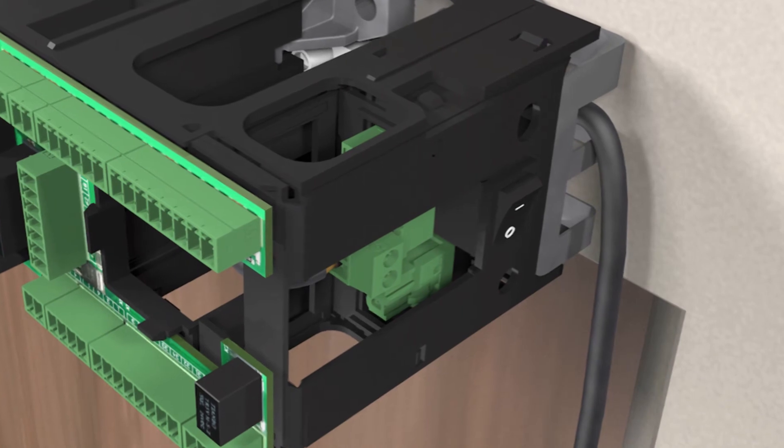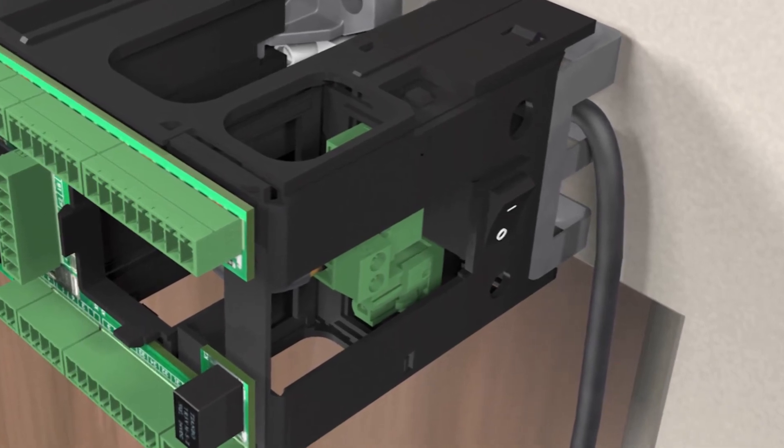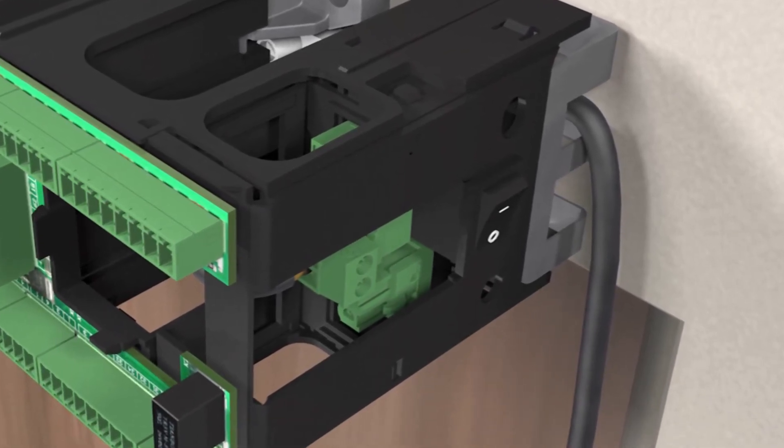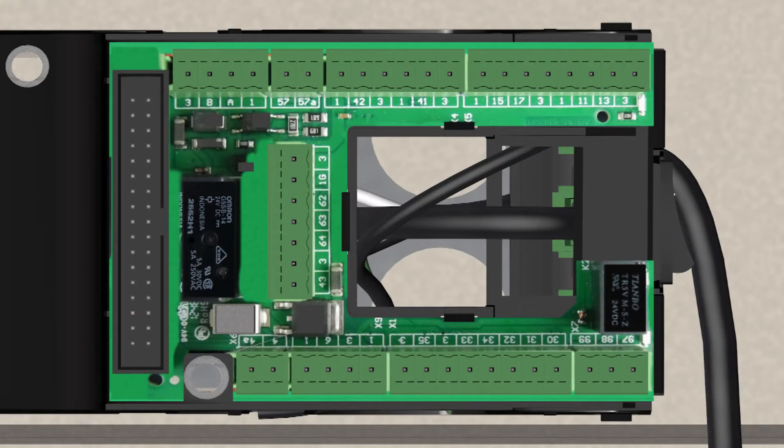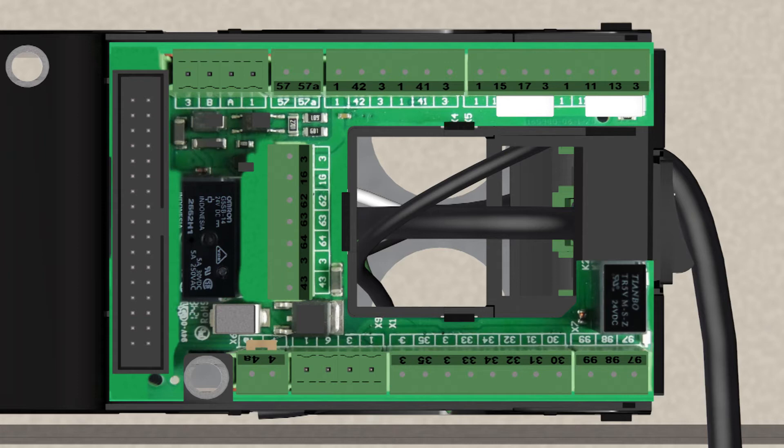Be sure the operator is powered off before attempting any wiring due to potential electric shock. The terminals for the connection board are shipped loose in a plastic bag. Before any attempt is made to program the operator, the terminal blocks need to be installed on the connection board.